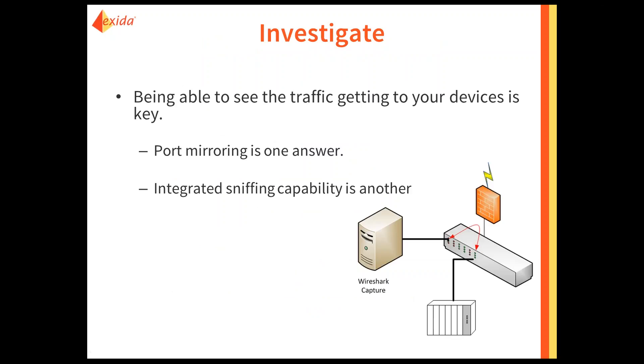How do we go about getting the information we need to populate our Modbus deep packet inspection devices? The first thing is we have to actually see what's going on on the network. This takes quite a bit of networking experience, because you have to understand what is going on in the network to begin with in order to know what to do with it. We have two methods: one is port mirroring — most industrial switches allow you to mirror ports to a single port which you can then use as a capturing device. The other is that some of the devices have an integrated sniffing capability.